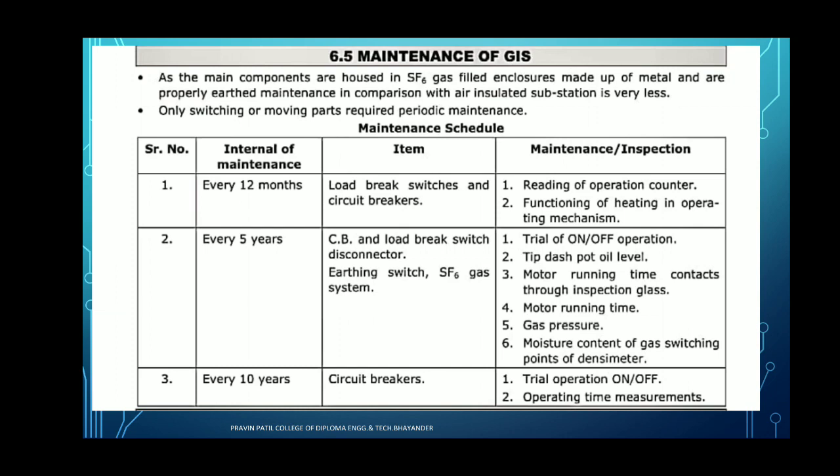We have to see some points of maintenance of the GIS substation. Internal maintenance means which parts we have to check — inspection of the parts. First, every 12 months we have to check the load break switches and circuit breaker. These things are checked within every 12 months: reading of the operation counter, and functioning of the heating in operating mechanism. This is the first maintenance requirement for the gas insulated substation.